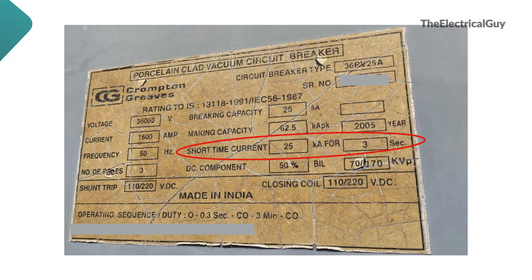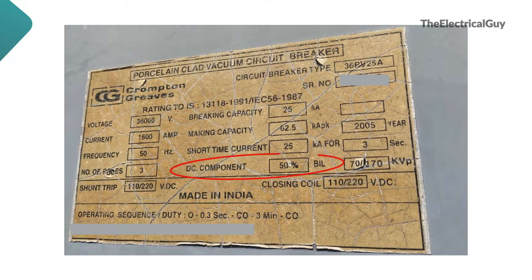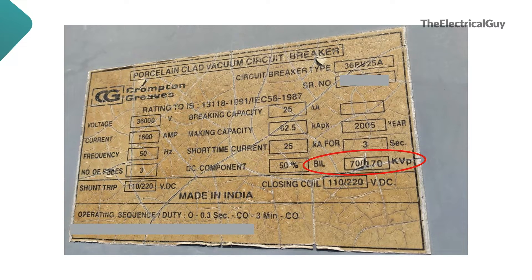Next is short-time current — this is the short-time current of the system which may occur in case of fault, and this current may remain in the system for 3 seconds. Our breaker is also capable of breaking 25 kA short-circuit current. Next is DC component. Short-circuit breaking current can be expressed in two values: the RMS value of the AC component and the DC component at the time of contact separation. On the nameplate, it is mentioned as 50%.